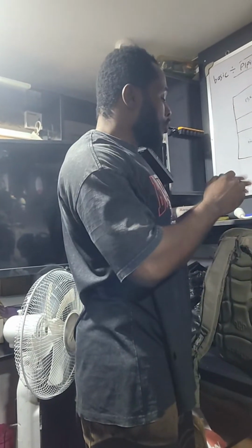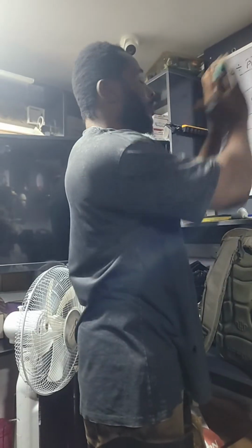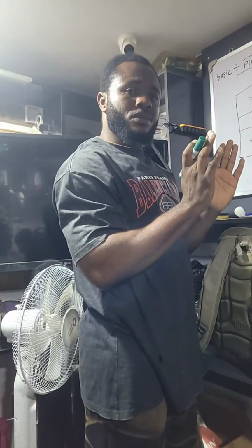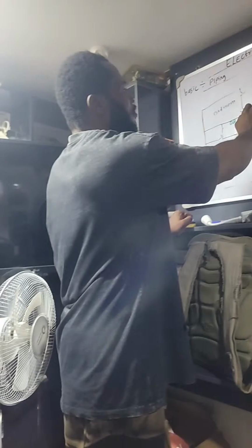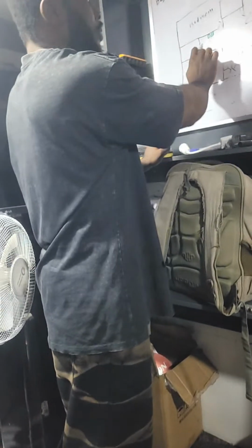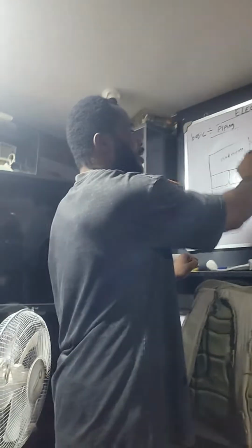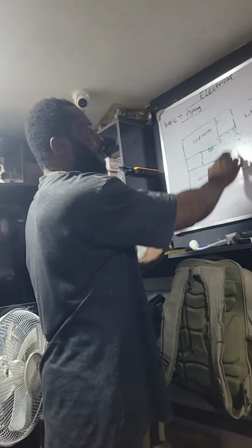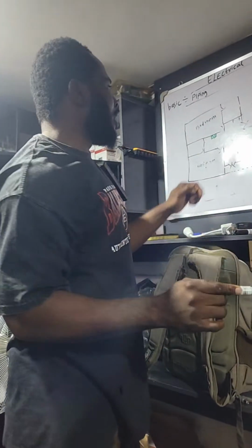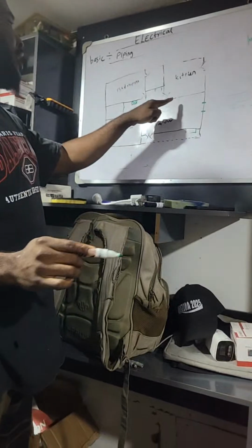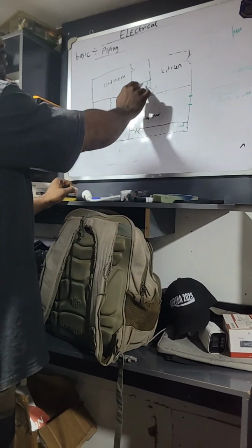Then secondly, you consider space for maintenance. What do I mean by space for maintenance? This is the kitchen, this is the toilet side. Now, you decide to put your DB here. I chose the DB here, and I'll tell you why. Then, in the sitting room, this place is an open side. When you are doing maintenance, you need to be moving to the kitchen all the time. The ladder you put is obstructing this space, and whatever you're doing will make the people in the parlor uncomfortable.